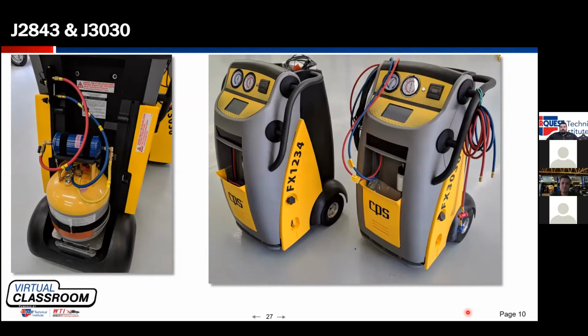So if I have the machine set up for 134A and a 1234YF car comes into the shop, what I'd have to do is start a process to change the machine from a 134A machine to a 1234YF machine. I would initiate the process through the machine's controls. The machine is going to evacuate all of the refrigerant into the tank and purge the internal plumbing. We would then open the back of the machine, remove the 134A tank and filter and hoses. From the front of the machine, remove the service hoses and swap in the 1234YF tank and hoses, at which point, finish the process. Now I've got a 1234YF machine sitting in front of me. I finish that car, I can go back to an R134A machine.